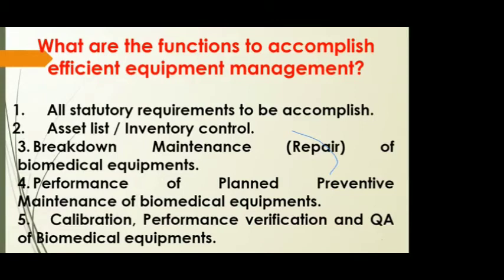If the problem is repeating periodically, then you need to make an RCA, root cause analysis, and the CAPA should be maintained so that the problem does not repeat again. And this indicator is required for the NABH. During audit time, they will ask how many breakdown hours there were for a particular equipment and how many times it was repeated. So this is the main register you have to maintain.